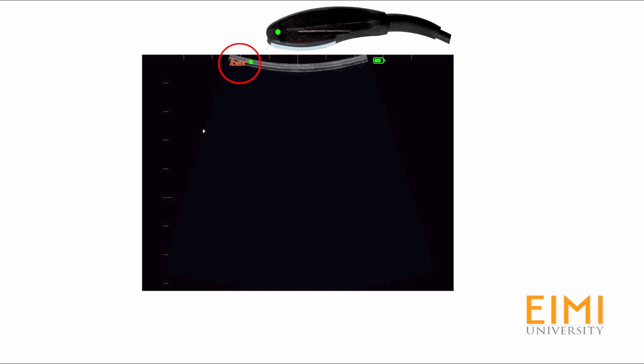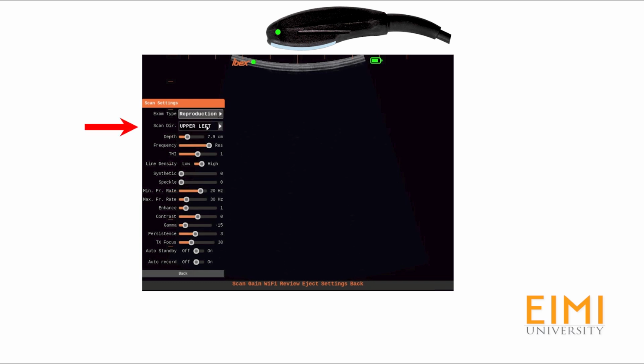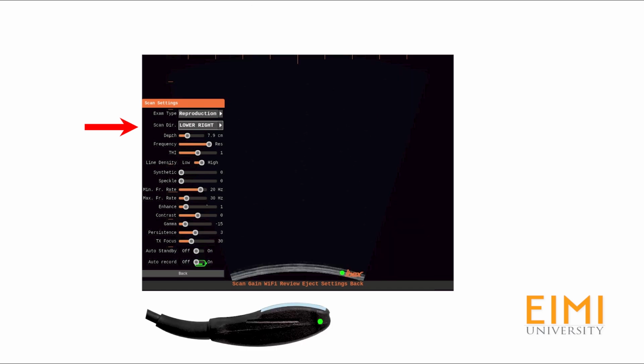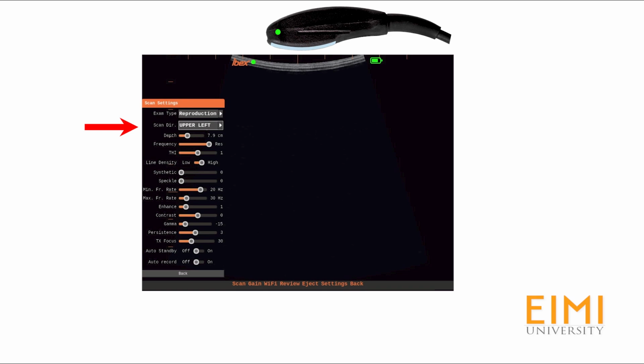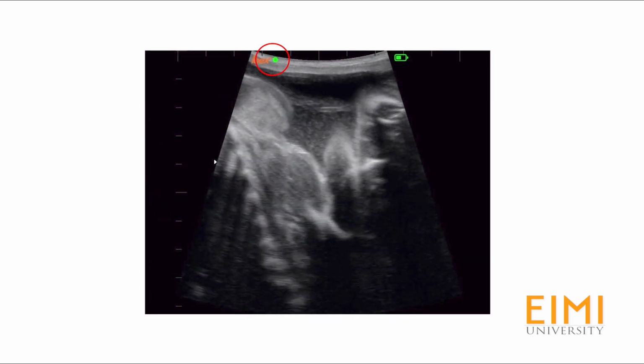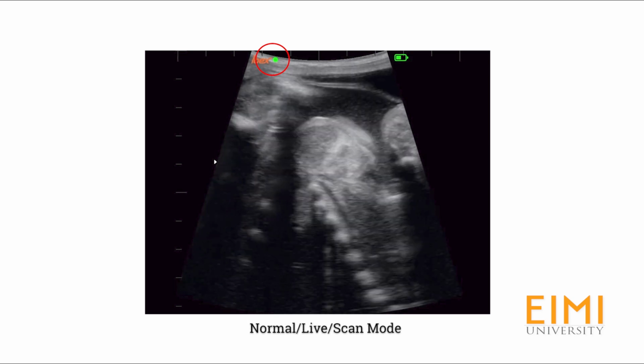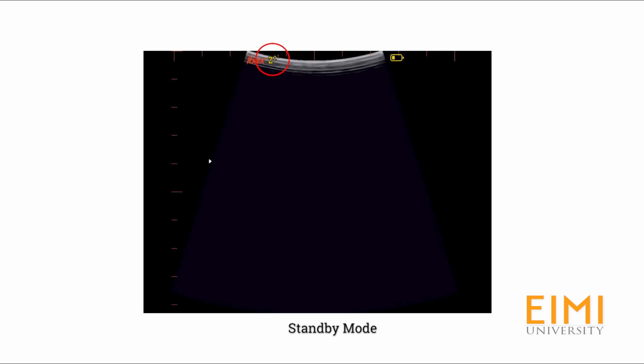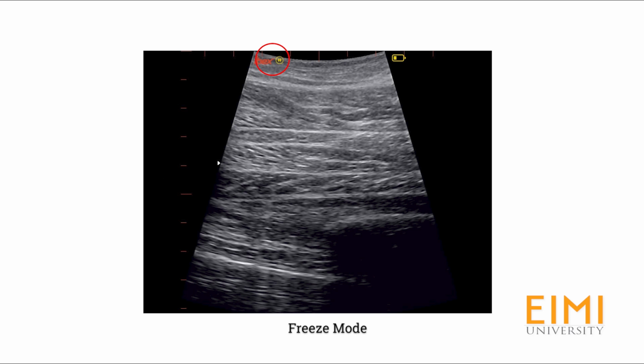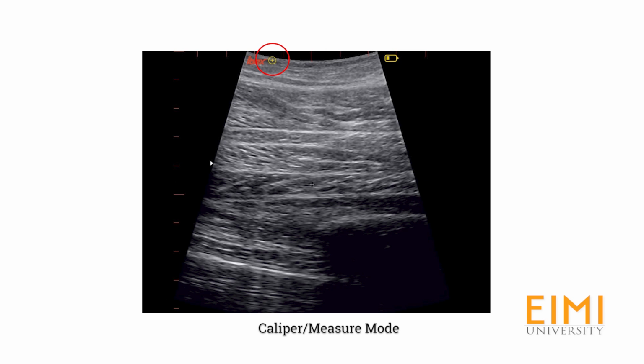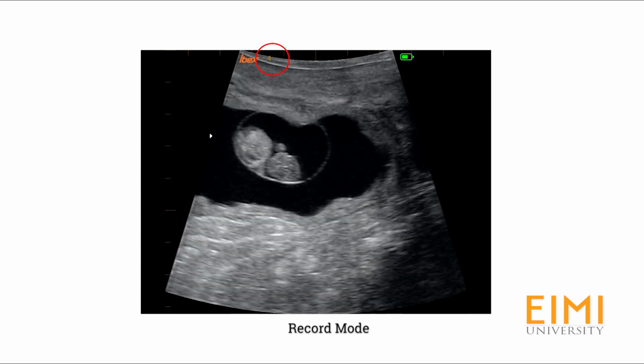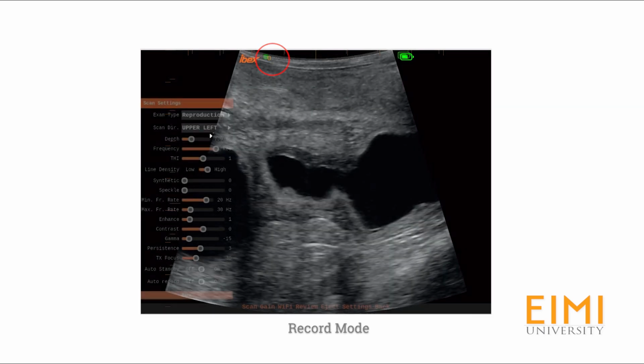Scan direction is indicated by the Ibex logo on screen. This marker corresponds to the cranial or forward tip of the probe head. To change the screen orientation, locate Scan Direction under the Scan menu. Next to the marker, you'll see a status indicator. In live scanning mode, this is a green dot. When standby mode is in effect, you'll see 3 Z's indicating that the probe is asleep. When the freeze key is activated, the indicator is a pause symbol. In measure mode, it's a circled plus sign. During recording, an orange dot flashes with a timer counting up or down depending upon the record settings.